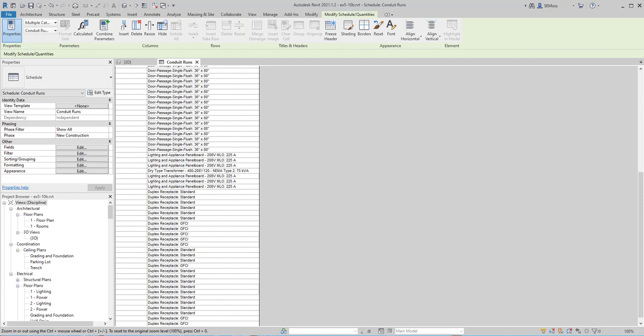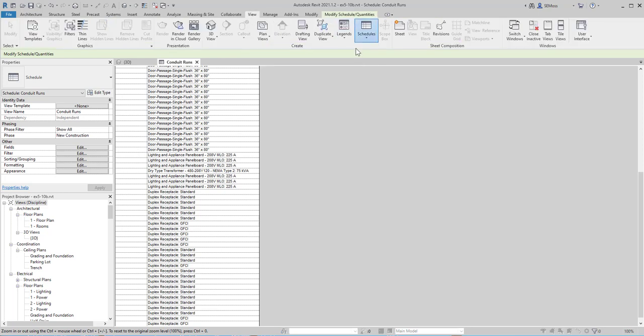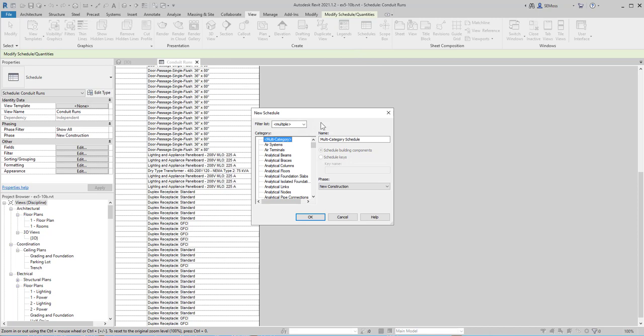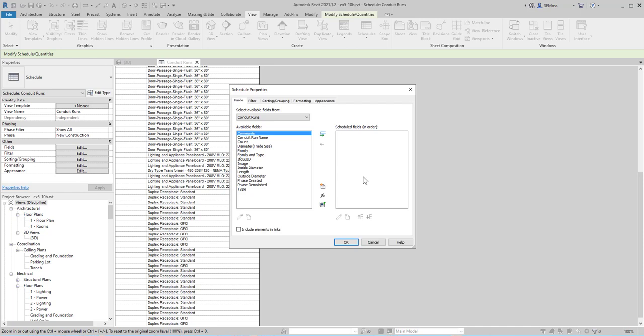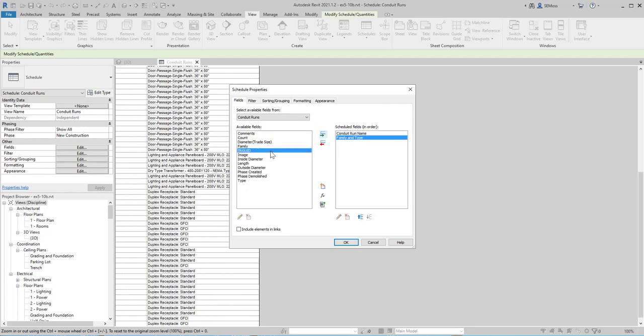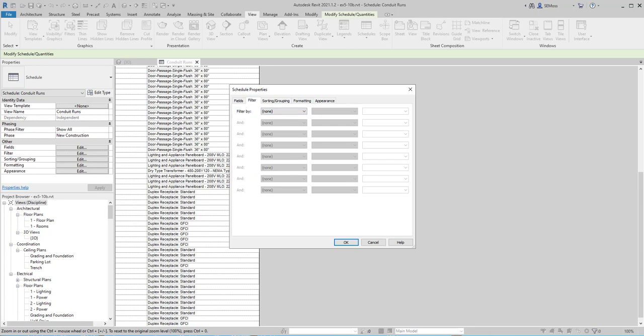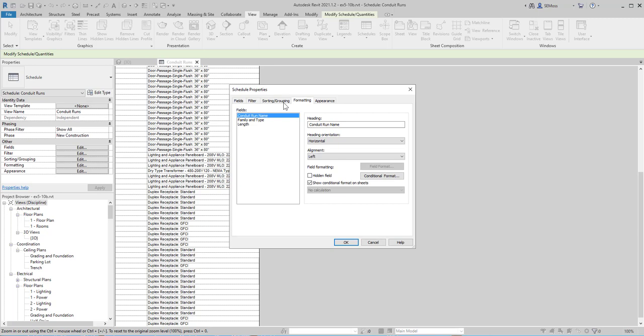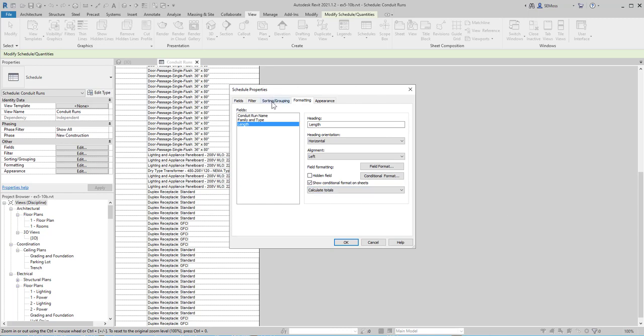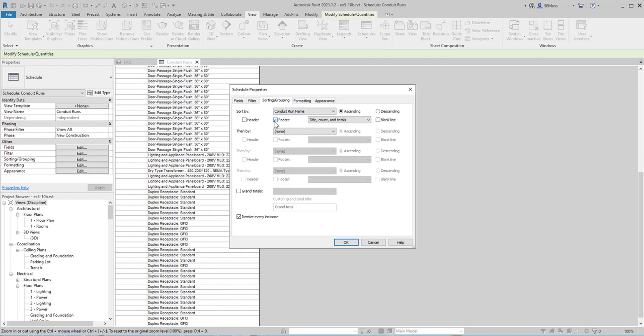Now we're going to create another schedule. I'm going to go to View, Schedule, Schedule Quantities, and this time I'm going to highlight Conduit Runs and call it Conduit Run Schedule, then say OK. I'll put in the Conduit Run Name, the Family and Type, and the Length. On the Filter tab, I'm going to set it so it doesn't filter by anything. Then on the Formatting tab, I'll highlight Length and enable Calculate Totals. Then going to Sorting and Grouping, I'll select Conduit Run Name, enable Footer, and say Totals Only, then click OK.